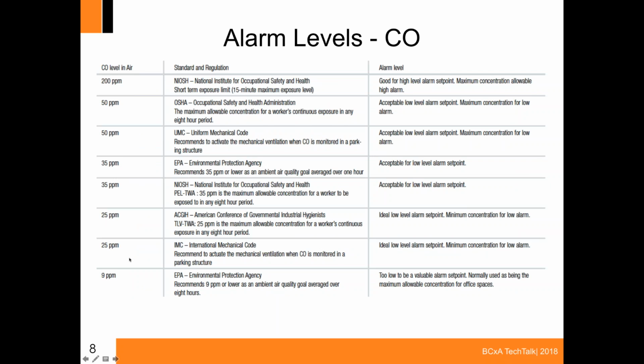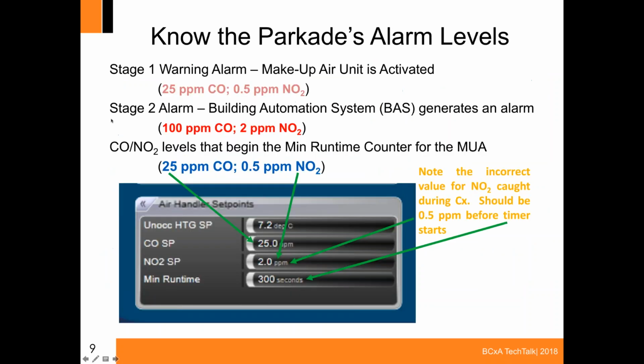So alarm levels for CO, this is from various codes in the US for standards and regulations of where you would start. 9 is too low, but anywhere from 25 to 50 is where you can start doing your low limit. As I said, we start our ventilation equipment, our makeup air units at 25, and then if we hit 100, that's where we alarm. For the NO2, it's at 0.5 parts per million, and then we alarm at 2. We never expect it to get up as high as 200 for CO or 5 for NO2. If it does, you have a problem.